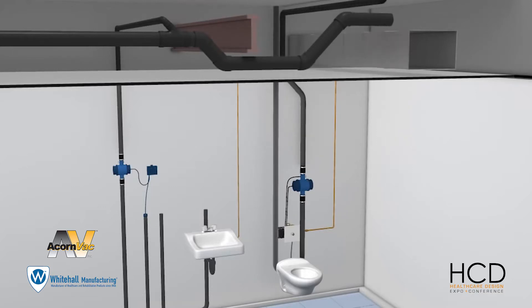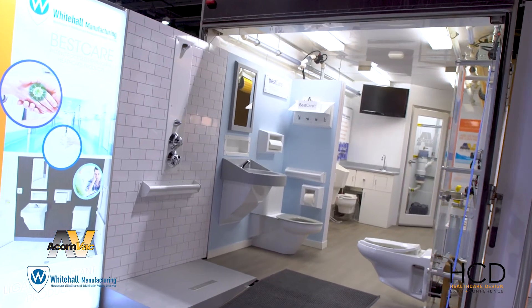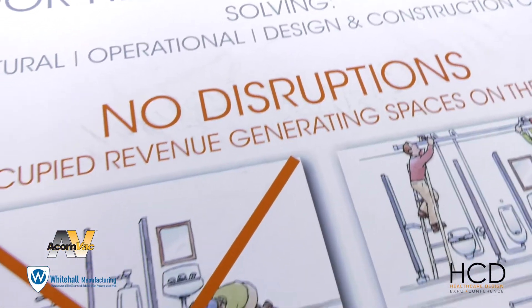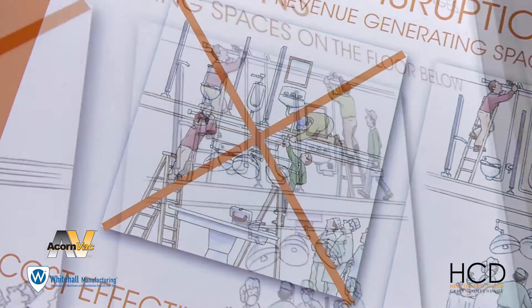Because it uses that vacuum interface, piping can be routed both vertically and horizontally. Vacuum plumbing allows you to save space because routing the piping through the facility without the need for continuous slope means the space between floors doesn't need to be as great. It allows renovation without disruption to adjacent areas of the facility and allows revenue-generating spaces to remain open while renovations are occurring.